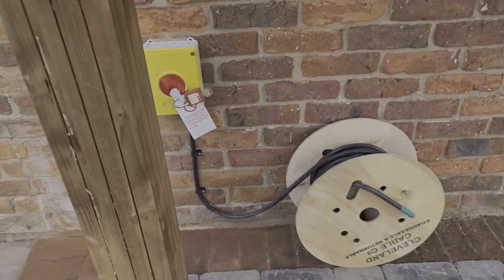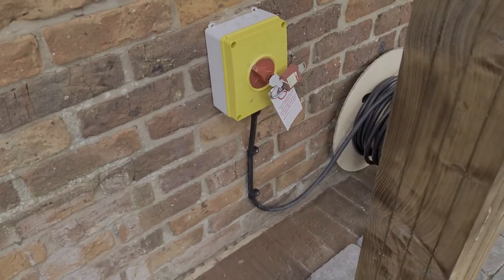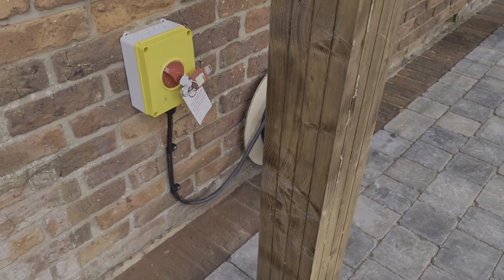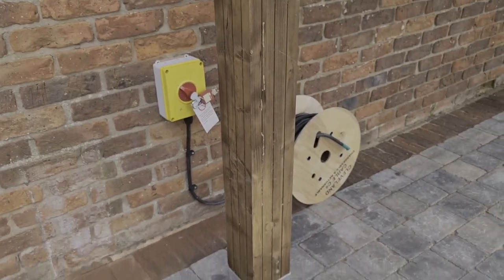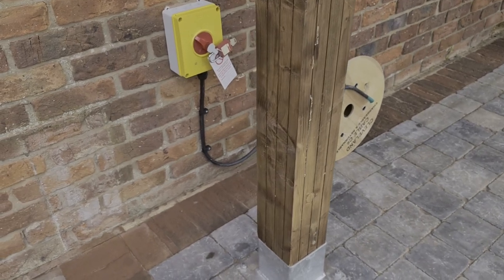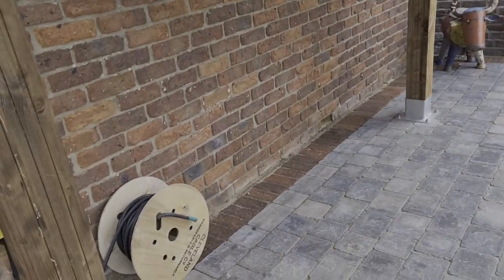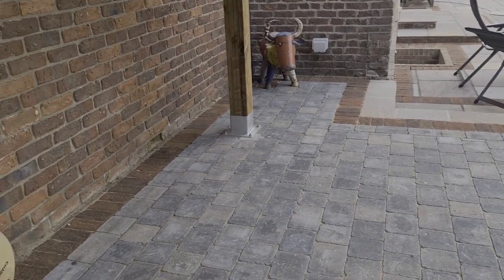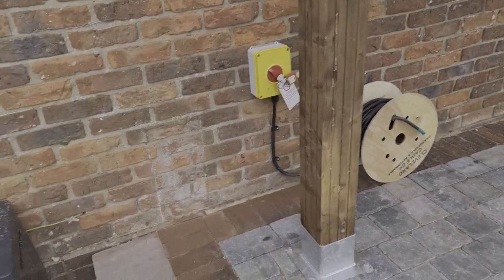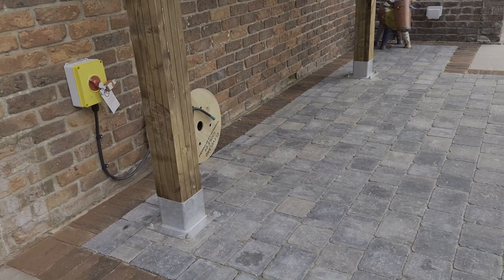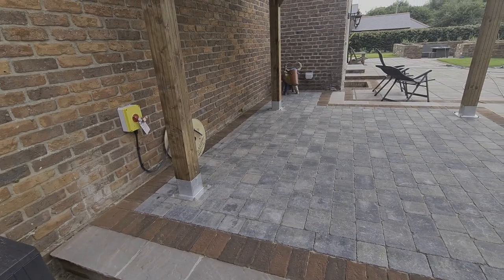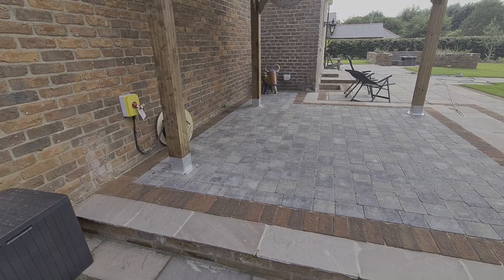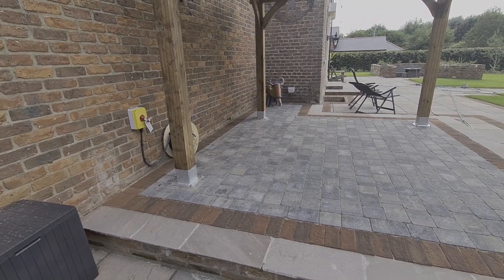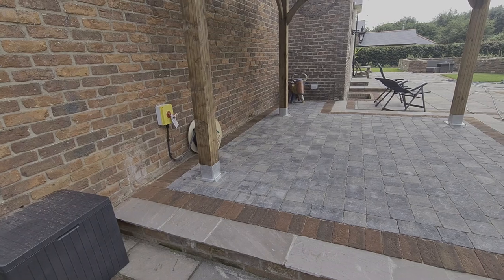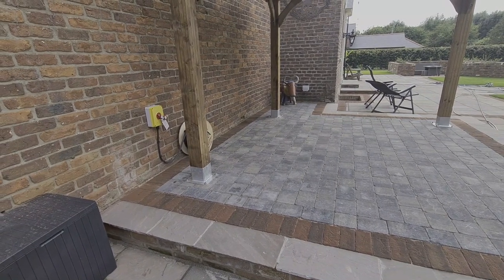So we've got the isolator on and locked off, ready for the hot tub installers, and we'll return to see how that pans out and exactly what the manufacturer's instructions are on the hot tub in particular. As I said, we've got the earth bond there, a light up there, and a TNCS supply socket over there. It's all in zone 2, and we'll have a chat through the rest of this video about whether you can connect the earth straight into the hot tub, or if you should be installing an earth electrode, and the various reasons for that - step voltage, the loss of the PEN conductor could be an issue. I'm going to give my opinions on it shortly and explain exactly what we've done on this install.